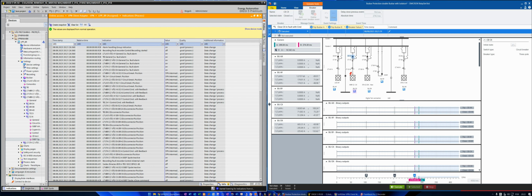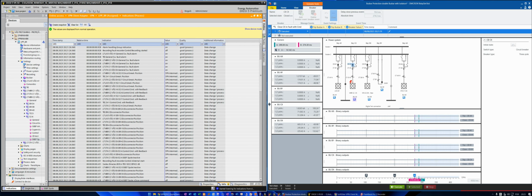So we see that in Siemens protection 7SS85, when you enable the end fault protection of your bay, you have more selectivity to faults that we can have between the circuit breaker and the CT when your circuit breaker is open, because when you enable your bus bar protection, you will not see this current if the circuit breaker is open.